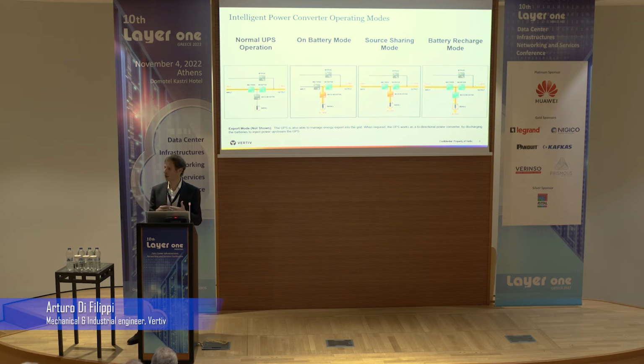You can do the source sharing mode, so part of the power is coming from the mains and part is coming from the battery, or even you can just decide to keep the power to the load unchanged, so it is in this case full load, but at the same time you get more from the grid to power the batteries. So in these operating modes, you see there is no indication that the flow can be in the other way. Our UPS could theoretically export power to the grid, but if we do that, the UPS changes function and turns into a bidirectional power converter that is closer to what we do with the PCS for the solar, and that's why this injection of power back to the grid needs to be carefully evaluated, and this is not something that we can provide as standard.